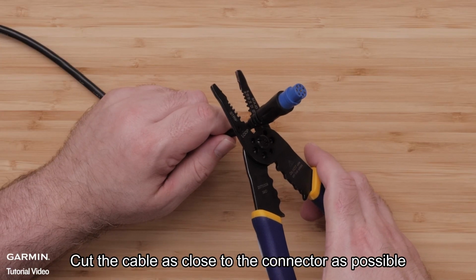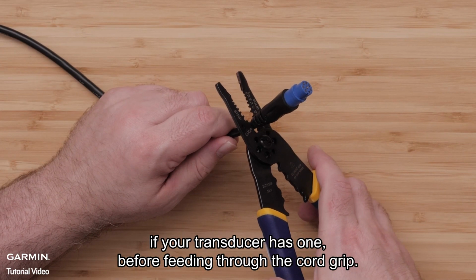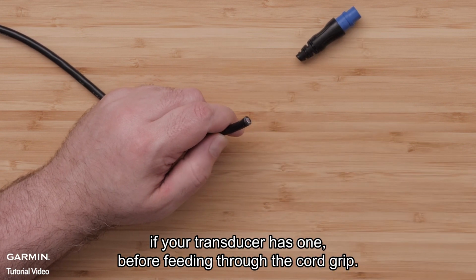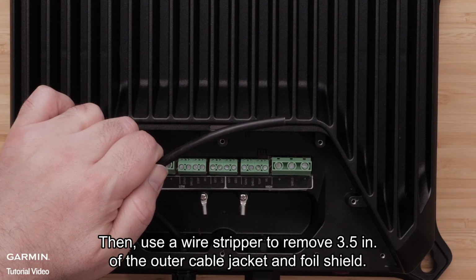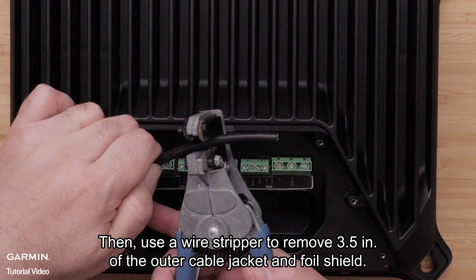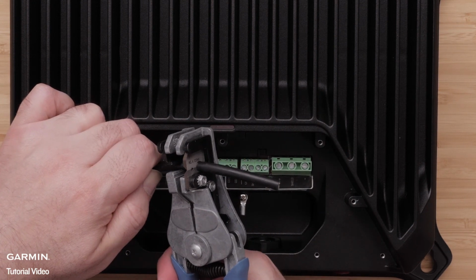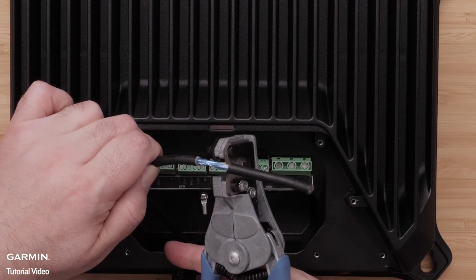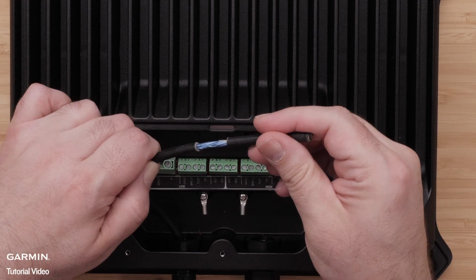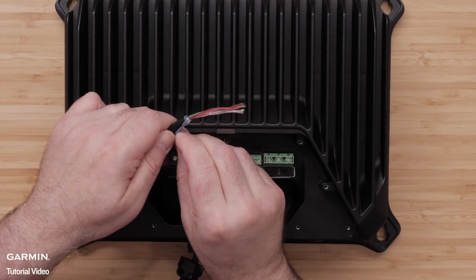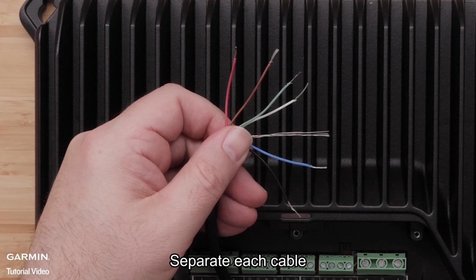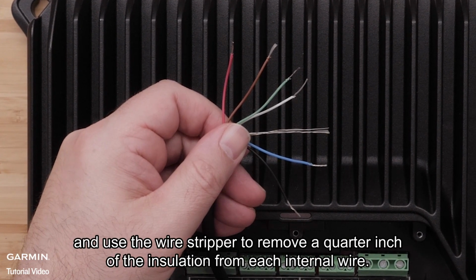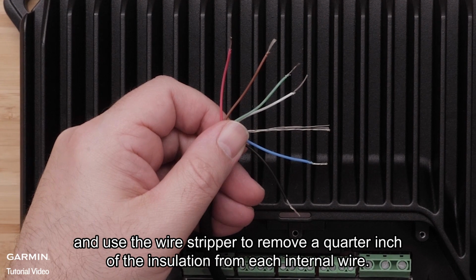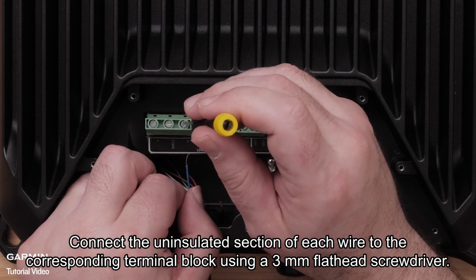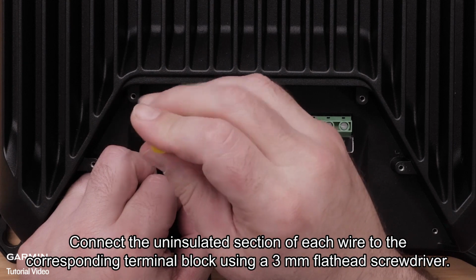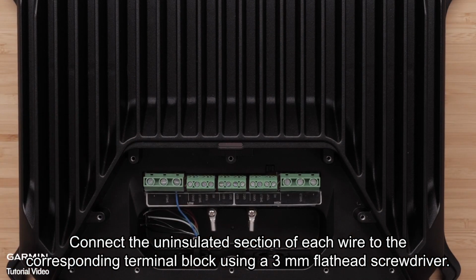Cut the transducer cable as close to the connector as possible if your transducer has one, before feeding through the cord grip. Then use a wire stripper to remove 3.5 inches of the outer cable jacket and foil shield. Separate each cable and use the wire stripper to remove a 1/4 inch of the insulation from each internal wire. Connect the uninsulated section of each wire to the corresponding terminal block using a 3mm flathead screwdriver.